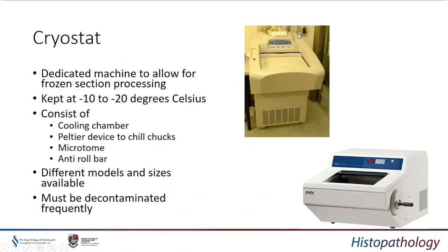There are full-size cryostats and also bench-top cryostats, so depending on your infrastructure these may be applicable. If you're going to do regular frozen sections, a larger piece of kit is more dependable. However, we are dealing with fresh frozen tissue and there is always a risk of infection, so the cryostat must be decontaminated frequently. That will take the equipment out of service, so it's important to ensure decontamination is not done when a frozen section may be requested.